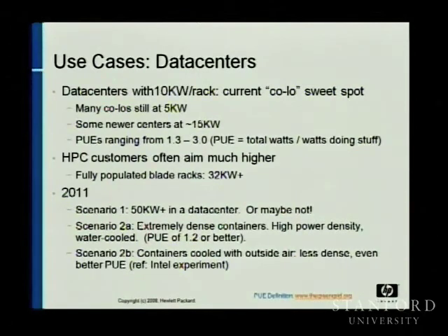So then the other question is, I just bought a shiny new server. Where the heck am I going to put it? It's not in your office because they're really noisy, offensive beasts, right? So you put them in these co-location centers. And when you figure out what most data centers can deal with, the old ones are at 5 kilowatts. The new shiny ones typically are at 10 kilowatts. This is per standard rack, which is 24 inches wide. The other guys have more than 10 kilowatts, but you can never actually find one. So 10 kilowatts is pretty standard.